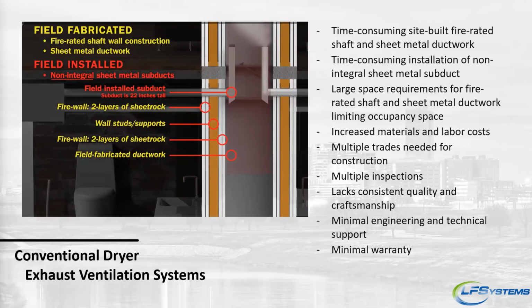So looking at field fabricated systems, a field fabricated shaft is a great option for some buildings, but there are some concerns about building a field fabricated shaft system, even using our low profile subducts. One of those is the time that it takes. It takes a lot of time to build a field fabricated shaft system. It also involves a couple different hands, because you have to have your shaft or your actual ductwork, and then you have to have your GC or your carpenter do double sheetrock, wall stud support, another layer of sheetrock. And so it takes a lot of space. You have to have multiple inspections.